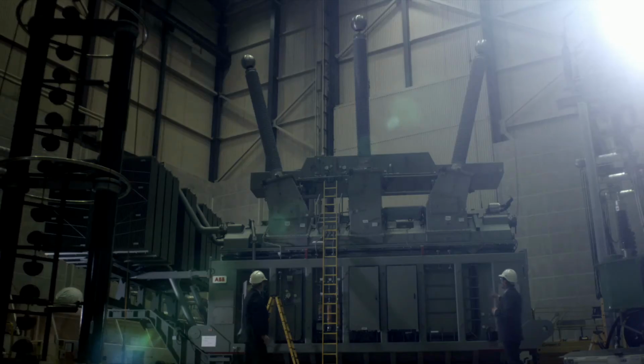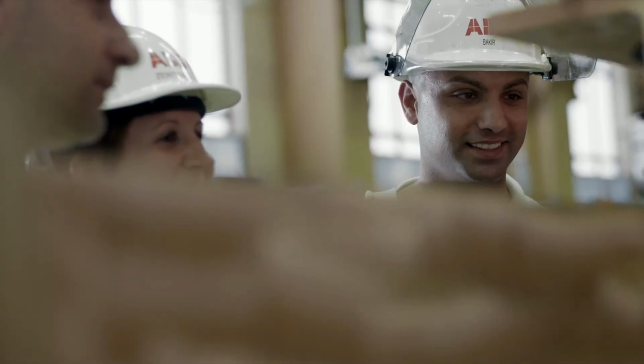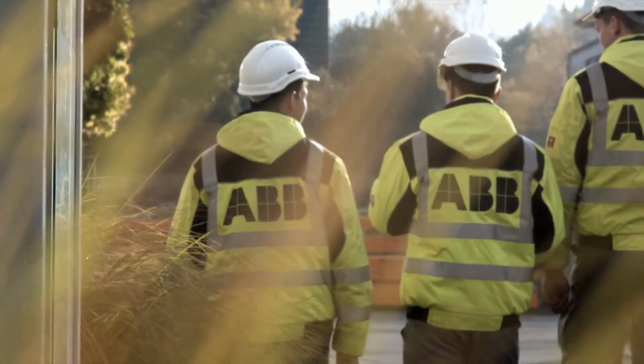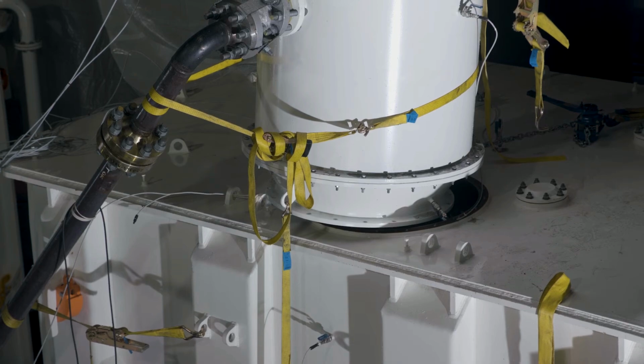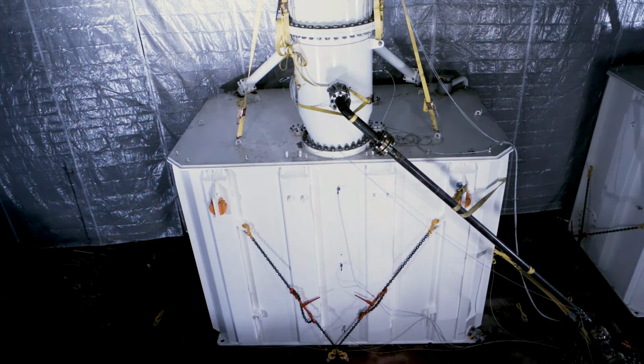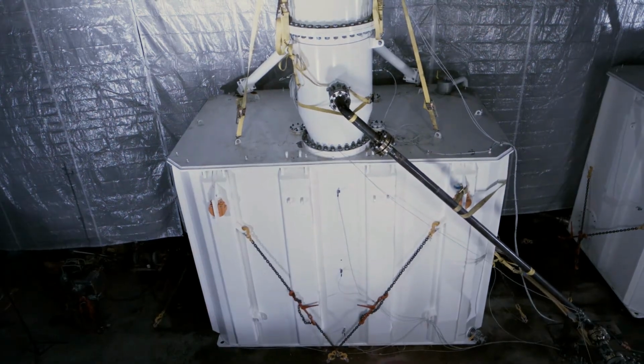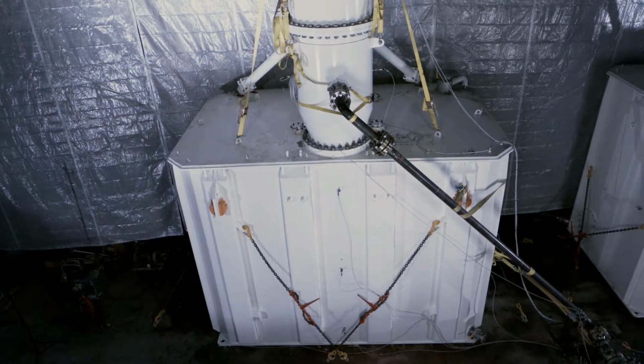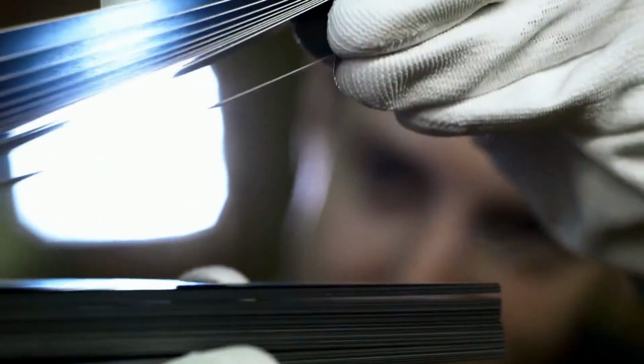More important, compatibility has limits. A unit has to match the electrical requirements of the position and connect to the physical system around it. Voltage, capacity, impedance, protection, physical connections, and site layout cannot be ignored because an emergency has begun. A spare that is useful for one family of substations may be unsuitable for another.